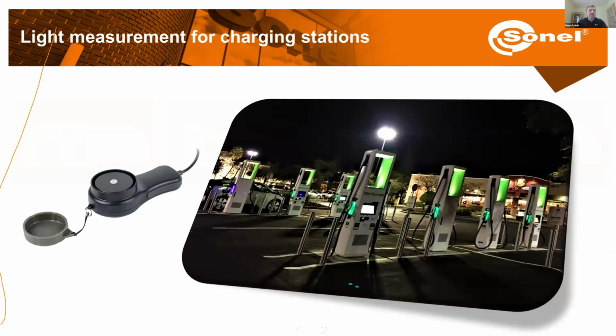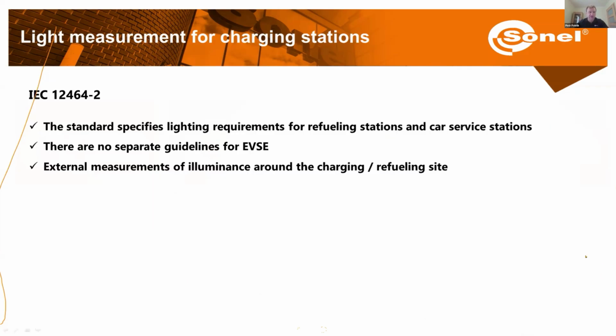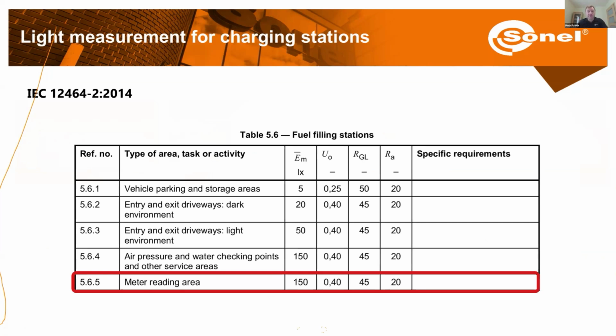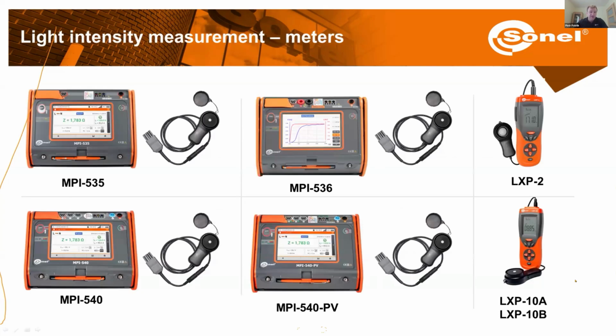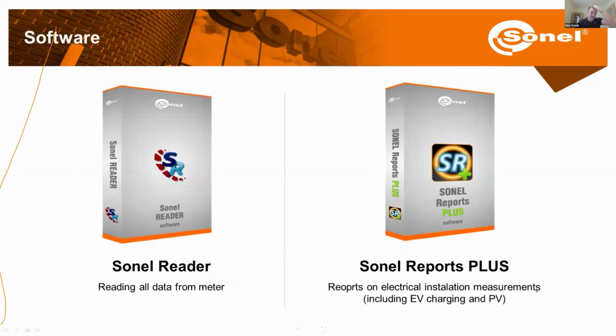Okay, now these were all the measurements of electrical safety, but we have some other measurements. For example, there's a requirement to check the light intensity at a meter reading area. That is described by IEC 12464, and it applies generally to fueling stations. The standard does not differentiate whether the fuel is gasoline, electricity or any other type. It just says it's a car fueling station, and a meter reading area needs to have at least 150 lux of light. The possibilities are either to use Sonel lux meters of the LXP series, or, whenever you have the multifunction meter, you can get the lux meter probe, which is an optional accessory to this meter, and we can perform the light intensity measurement.